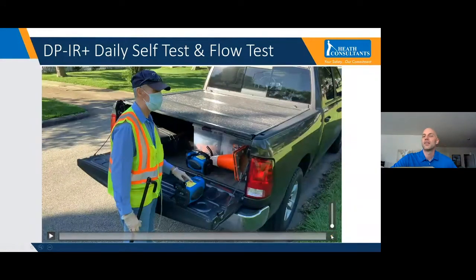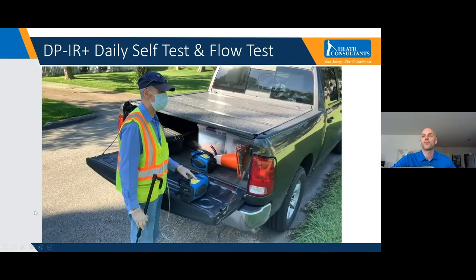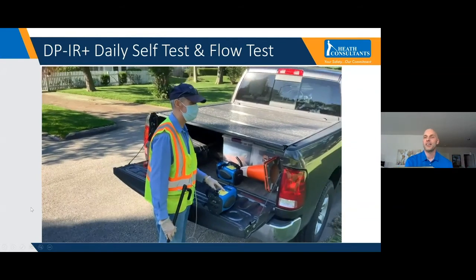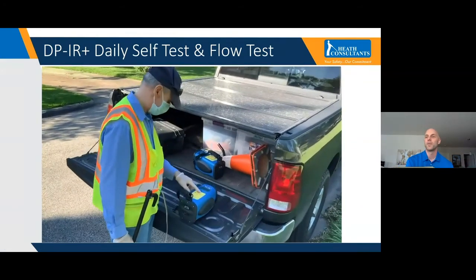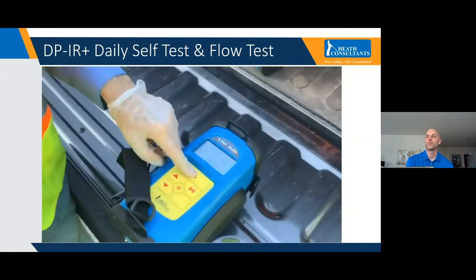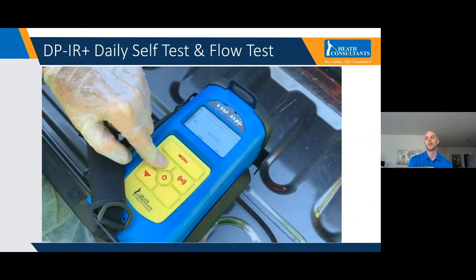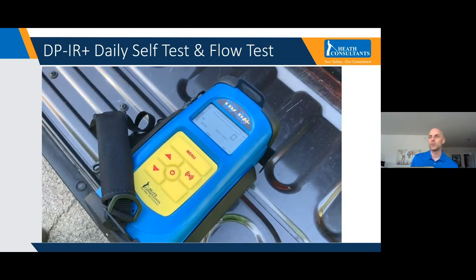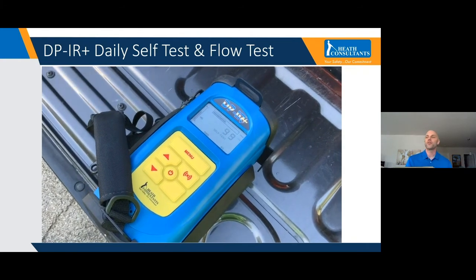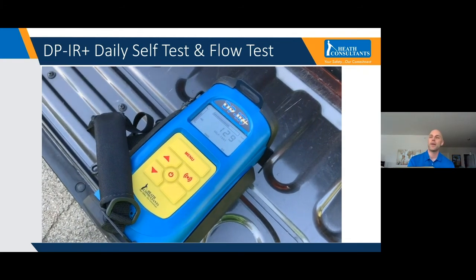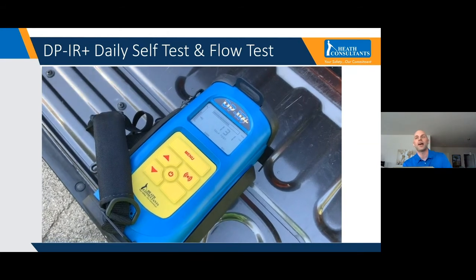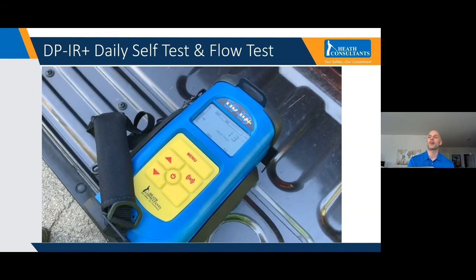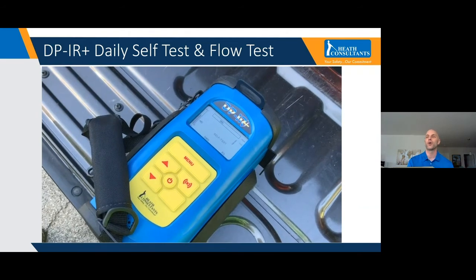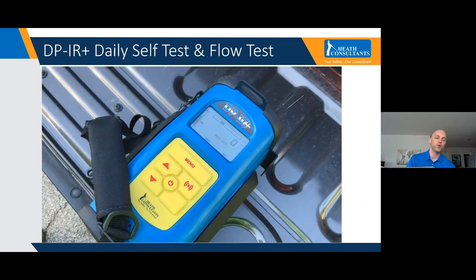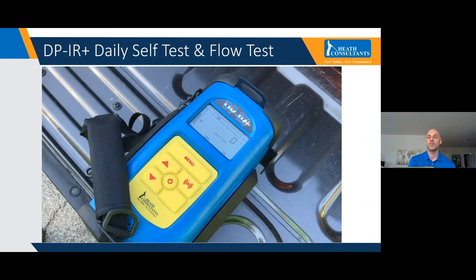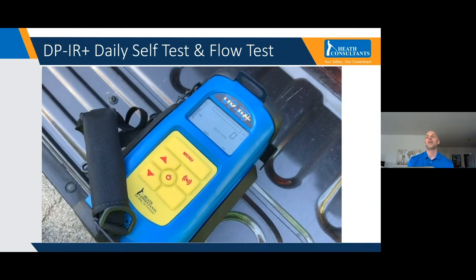So this is Roy, performing the self-test the other day, just to show you how quick and simple it is. You press the menu button on the screen, press the up arrow, and it begins to perform the self-test. You see the numbers start to increase when that methane cell passes within the light path. You'll see two different numbers that you don't really need to pay attention to, but if you were wondering, the first one it locks on to is what we call the uncorrected value of the instrument.